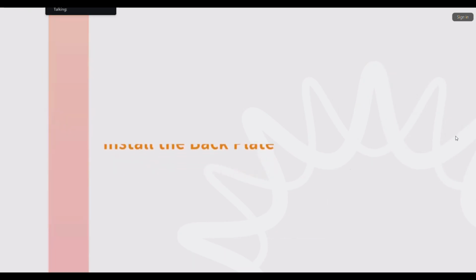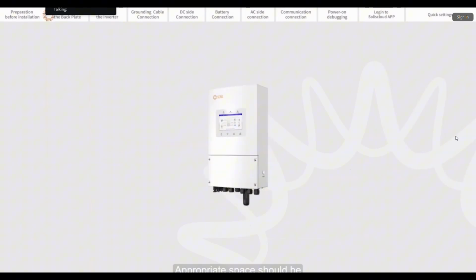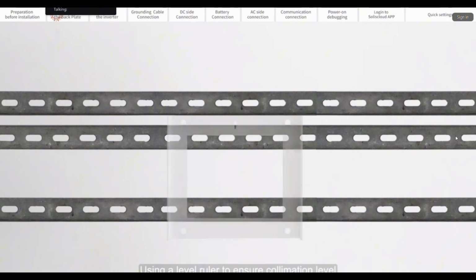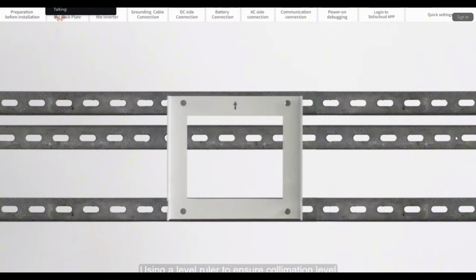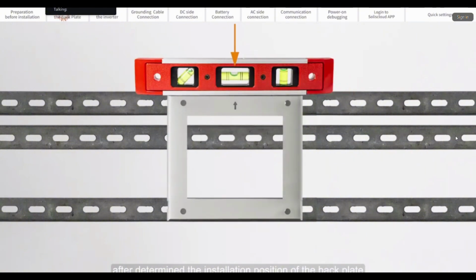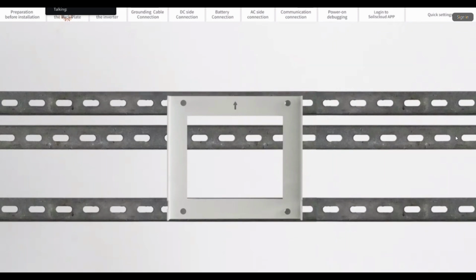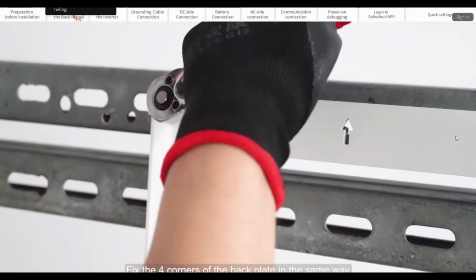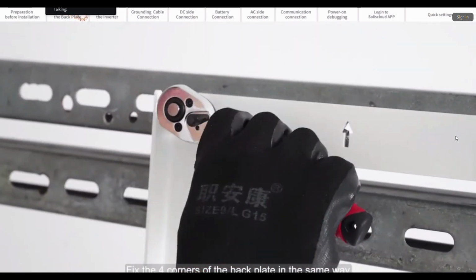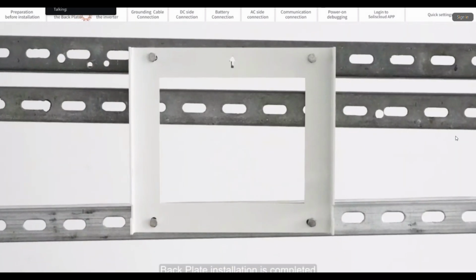Part 2. Install the backplate. Appropriate space should be reserved around the installation location of the inverter. Use a level ruler to ensure collimation level and determine the installation position of the backplate. Fix the backplate onto the wall using gaskets and nuts. Tighten the bolts. Fix the 4 corners of the backplate in the same way. The backplate installation is complete.